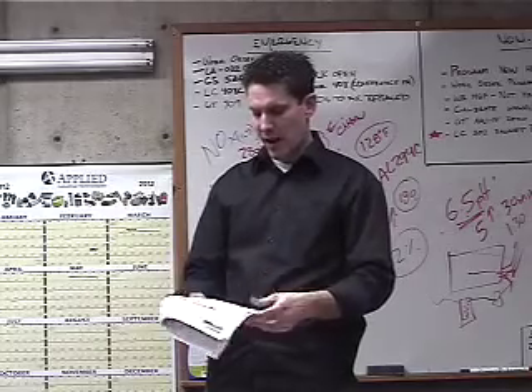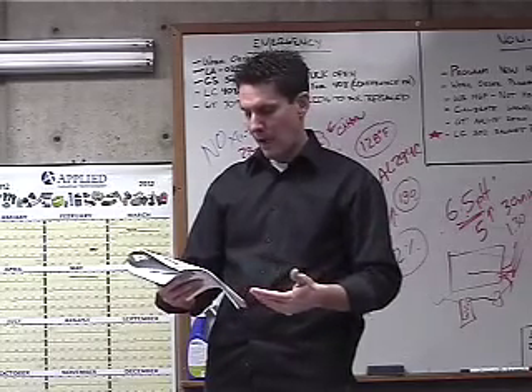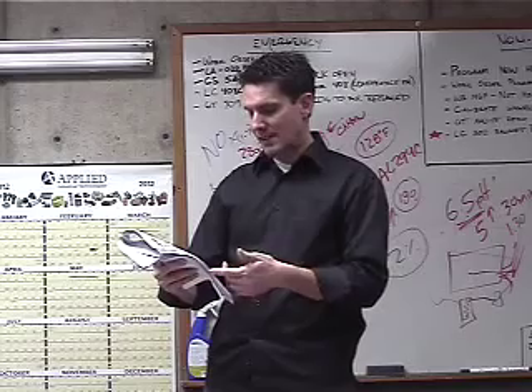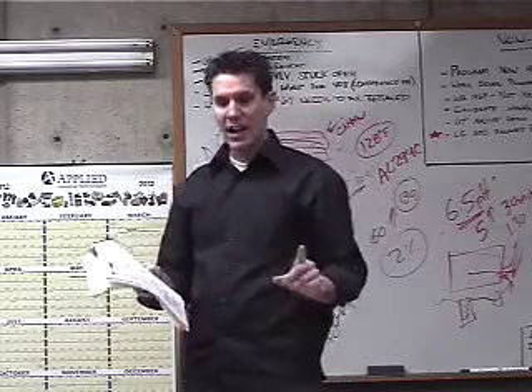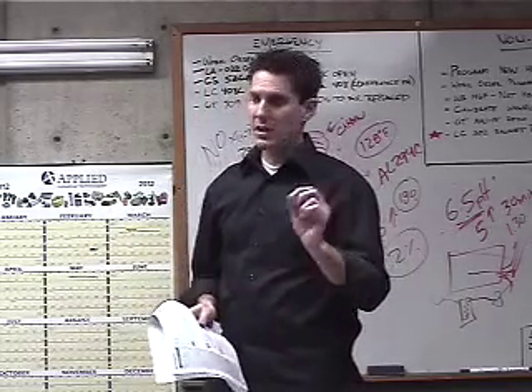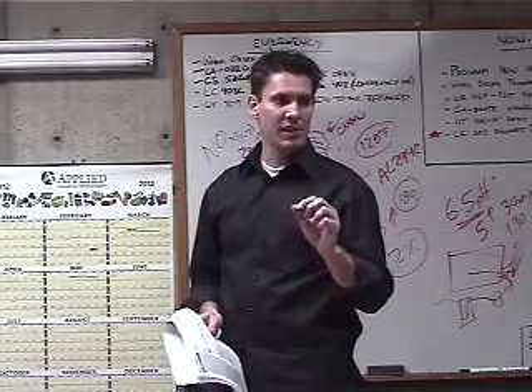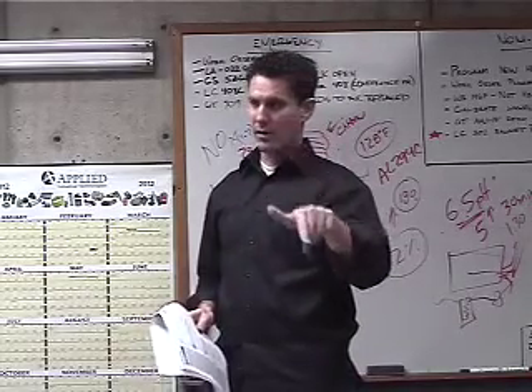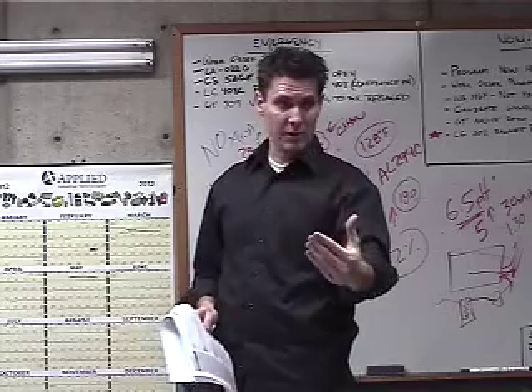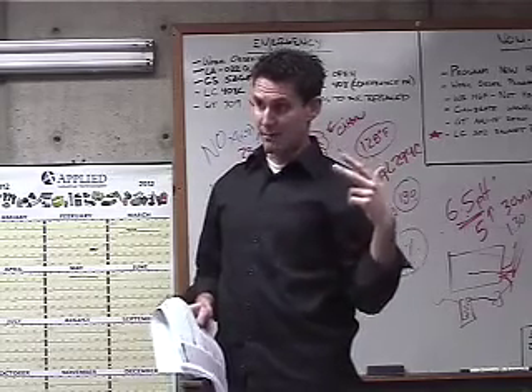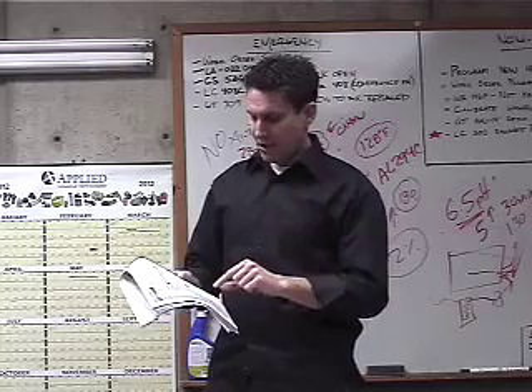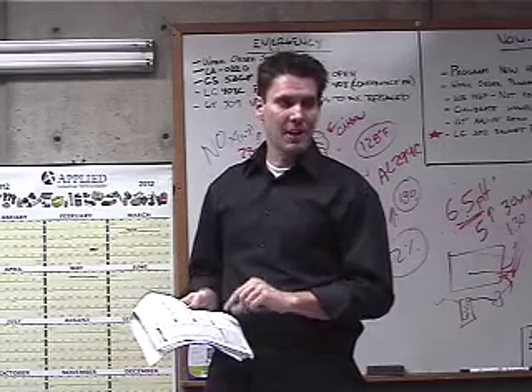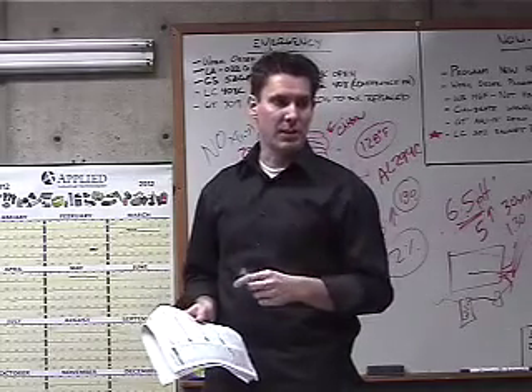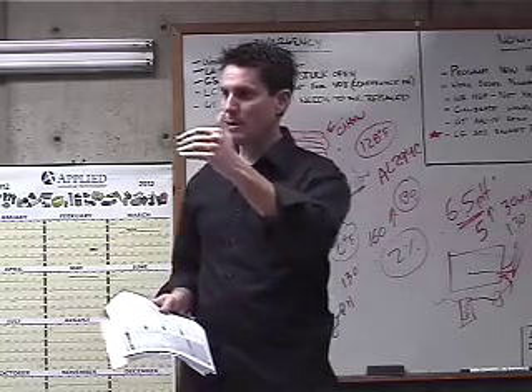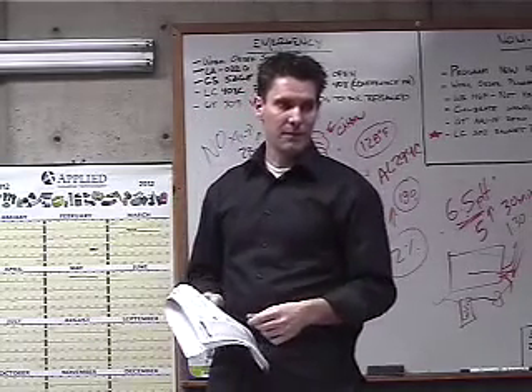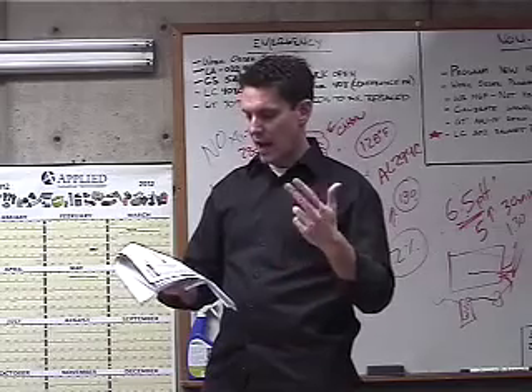So it gives you instructions on how to test your limit controls. Again, check your flue gas temperature at the outlet. Your flue gas, did you guys have a way to do that? If you can, it's not a bad idea to install a little thermometer, some type of temperature gauge, to look at your flue gas temperatures immediately leaving the boiler. If you see a drastic change in that, that's an instant sign that soot is building up in the boiler. If that temperature starts to go up, you're building up soot. Okay? So that's a good way to do that.